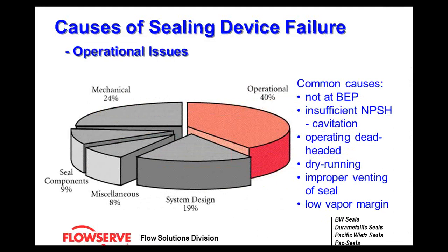Some common causes of operational failures: not operating the pump at the best efficiency point. Pumps are designed to operate in and around their best efficiency point — this is the optimal location for that pump to run. If you're outside of those regions, you can have flow characteristic problems which will cause a seal failure.